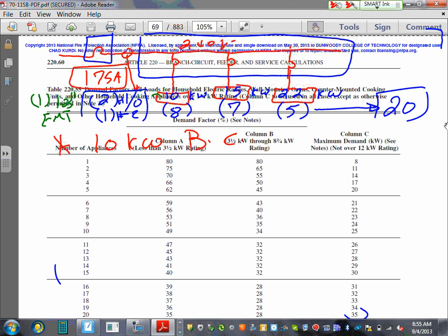So the code allows you for ranges to apply the table too, for branch circuits. The code allows you to apply the table. So from the same table, 220.55, we're looking at it right here. For 10 kW, one range will get you what? 8. Will get you 8. Right? Am I right? It's less than 12, get you 8. Did we do through the 8 or what? We just finished, did the kW. So let's do the 8.